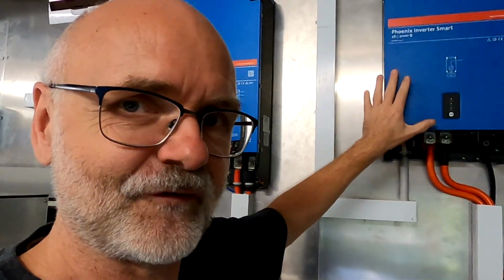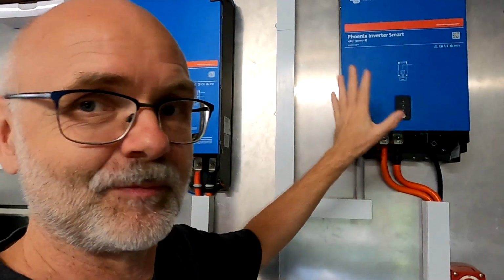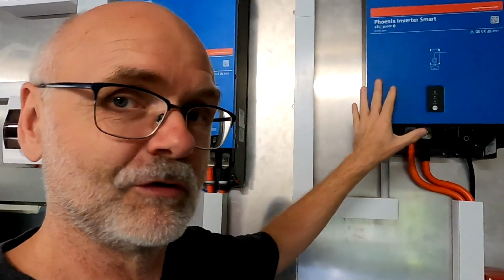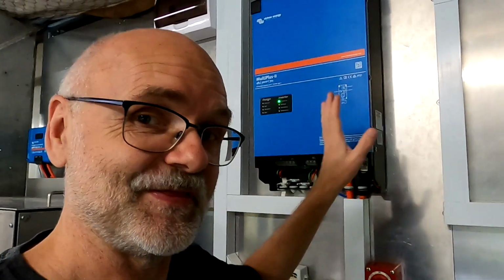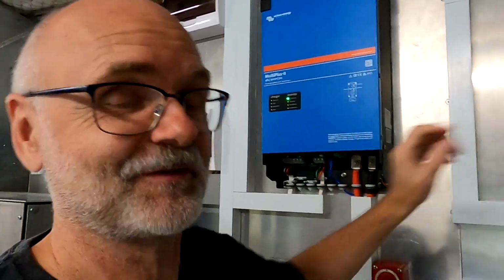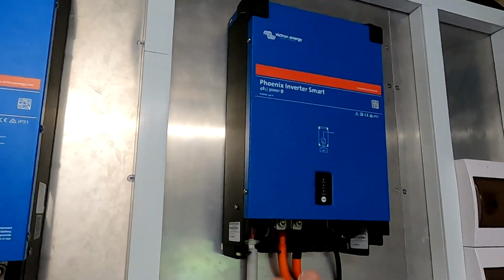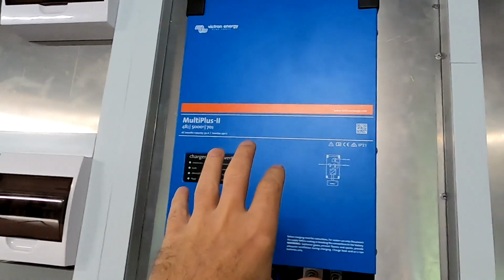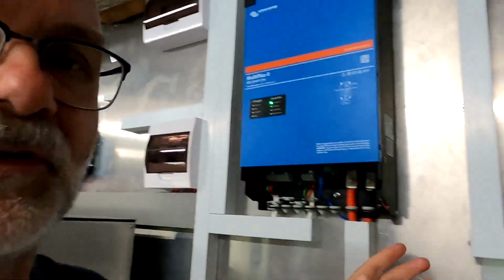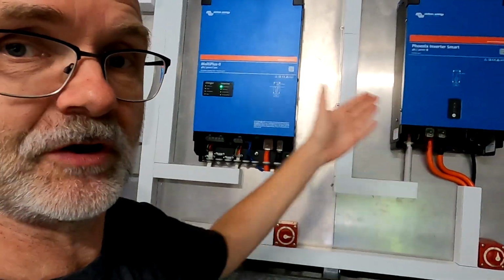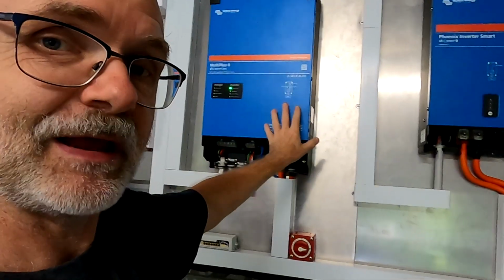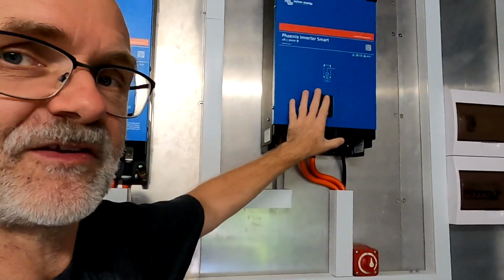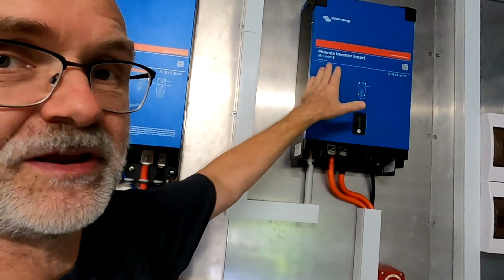It would mean the Phoenix inverter runs all the time and supplies power to our garage and loads all the time. The Multiplus then monitors the situation of the Phoenix, and if our load exceeds a certain threshold, which we can set up in the Multiplus, it will add additional power to support this load. So most of the load will be supplied by the Phoenix, and the Multiplus will add additional power as needed. The downside is both inverters would be running all the time - the Multiplus in standby, and the Phoenix doing all the work up until it's 3 kVA.